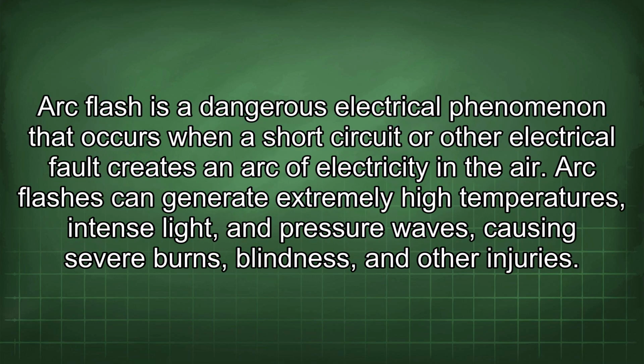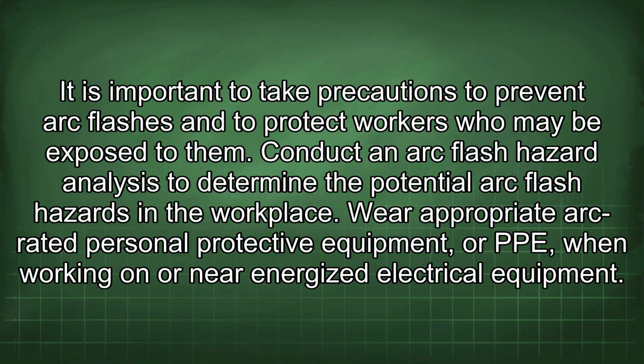Arc flash is a dangerous electrical phenomenon that occurs when a short circuit or other electrical fault creates an arc of electricity in the air. Arc flashes can generate extremely high temperatures, intense light, and pressure waves, causing severe burns, blindness, and other injuries. It is important to take precautions to prevent arc flashes and to protect workers who may be exposed to them.